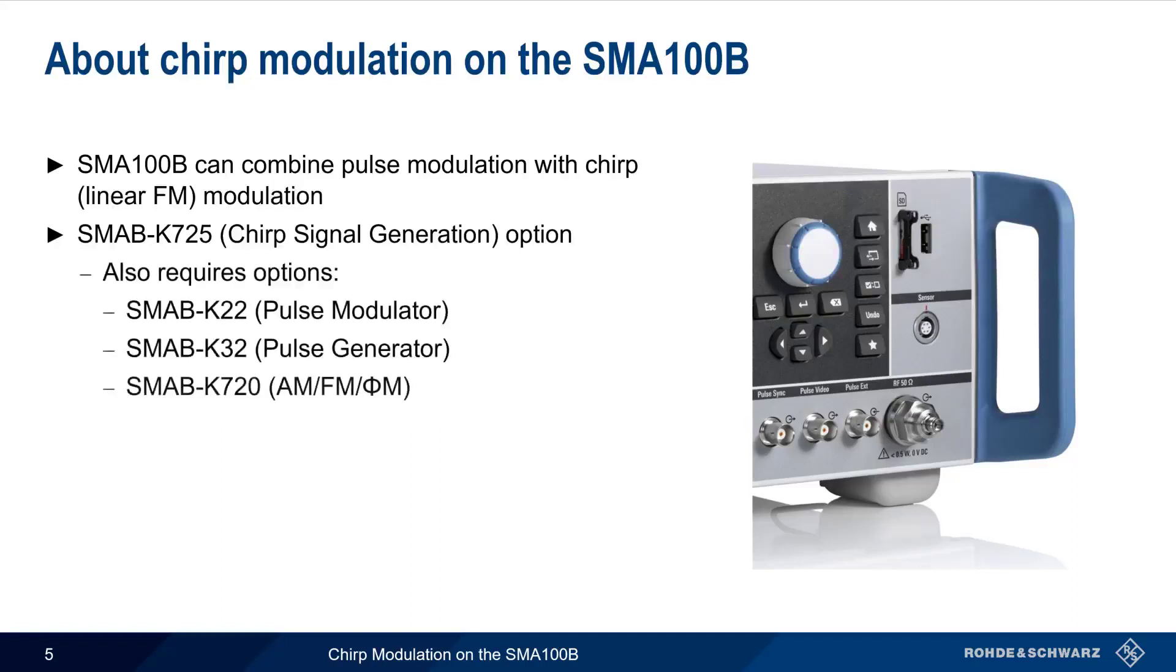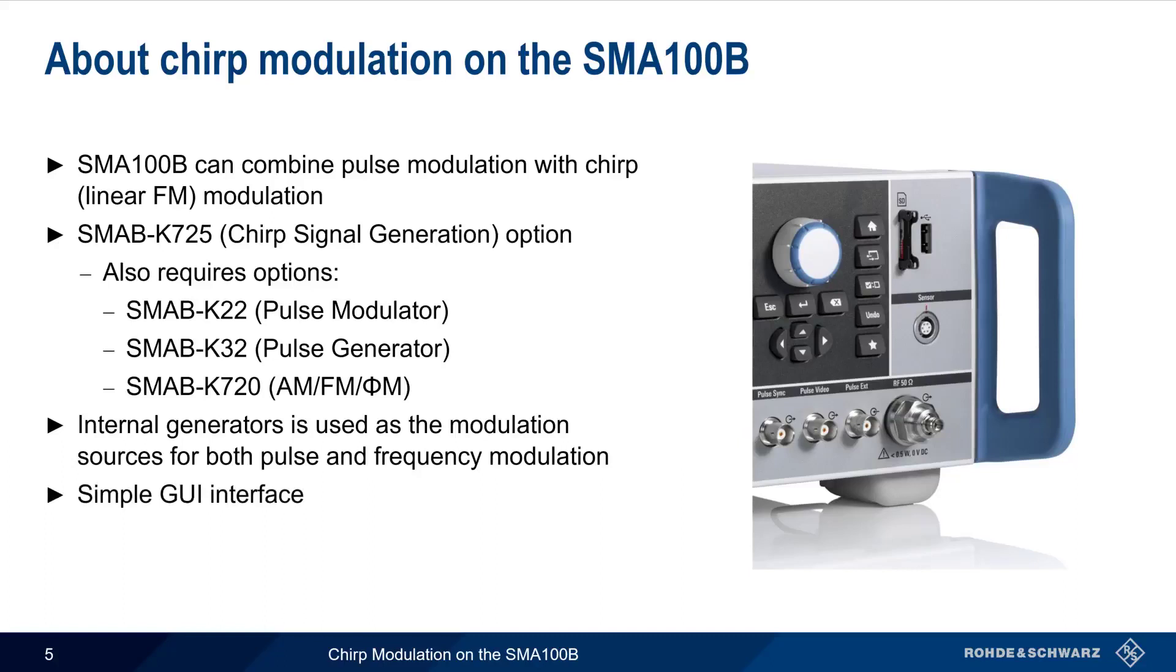The SMA-100B analog signal generator can combine pulse modulation with linear FM, or chirp modulation, to simulate this type of modulated radar pulse. Chirp signal generation is enabled by software option K725, and also requires options K22, K32, and K720. The SMA uses its own internal generators for creating both the pulse and frequency modulation, and in the remainder of this presentation, we will explain how to configure chirp modulation using the SMA's simple user interface.